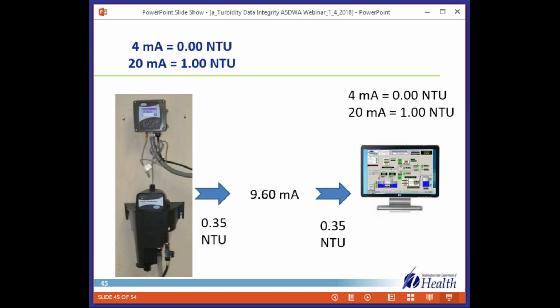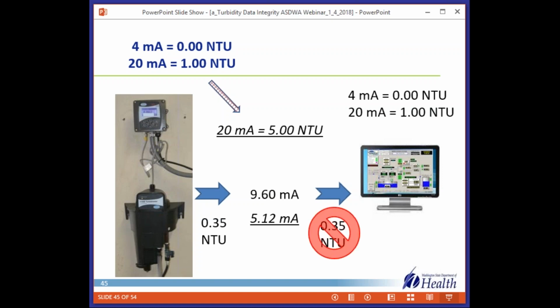So after our visit, let's say the operator decided, oh, I need to change to 0 to 5, but the operator only changed the controller and didn't change SCADA. So here's what might happen there. Instead of a 9.6 milliamp signal, the controller would send 5.12 milliamps. And now the SCADA, instead of picking up 0.35 NTU, reads 0.07 NTU. So no regulatory violation is detected there.